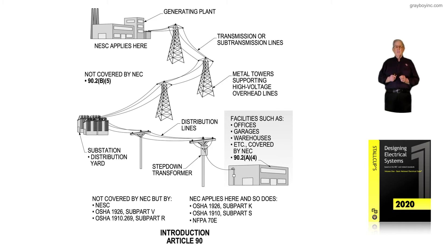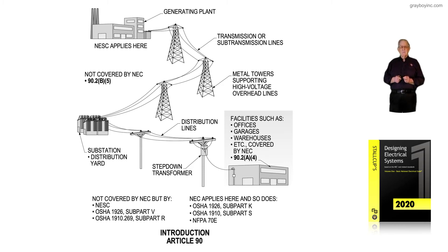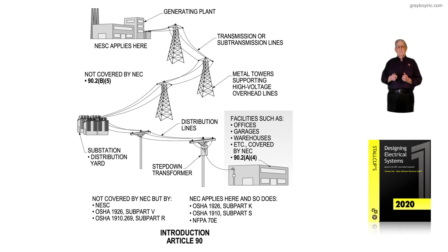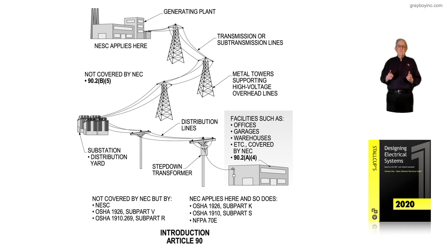On the load side, the service drop conductors connect to the conductors at the weather head at the building location — that is the service point — and from there the NEC takes over. It wouldn't matter if the office, facility, garage, or warehouse belonged to the utility; it would still be covered by the NEC in accordance with 90.2(A).